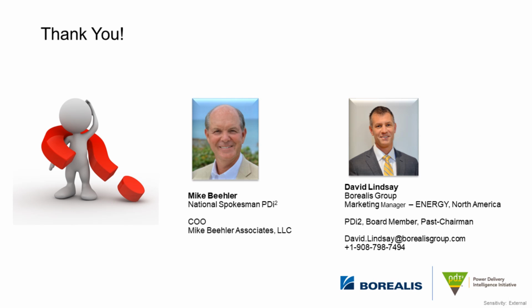Okay. Next question. This question comes from a utility. Does SuperCure result in more cross-link sites than conventional cure? So the answer to that is no. Doesn't result in more cross-link sites. What it does is offer more efficient cross-linking, and we can do it with less peroxide added to the material.